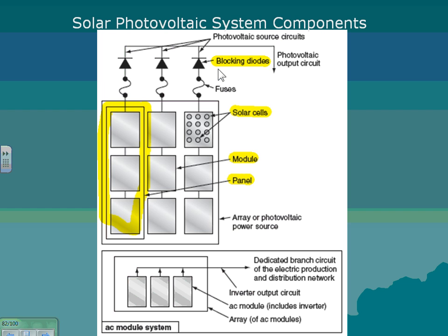To prevent one panel from feeding a fault to another panel, they will direct the traffic, if you can see. So, without getting too deep, these prevent one panel, instead of sending power to the grid, from sending power to another panel. So they have diodes to direct the traffic. And under certain circumstances, they have a fuse on every string. A good design is to have a fuse for every string. Here I'm holding a 500 volt string with 10 amps and with a fuse right here on the positive. On the positive, you put a fuse, a DC fuse.